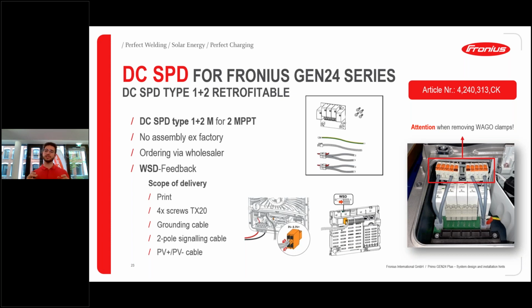So this is actually mounted underneath the connection terminals in the main body. And of course, it has the advantage that you don't need a separate box installed somewhere at the customer site. You can have all of the components inside the inverter and without any additional boxes. Very important to remember is that there is no ex-factory assembly, so you would need to order a separate component. You order this SPD from your wholesaler and build it in yourself. So it's not possible to order it assembled ex-factory. So if you're interested, just check with your wholesaler and order this article number, which we can see on the top right here. This is then the correct article number for this product.